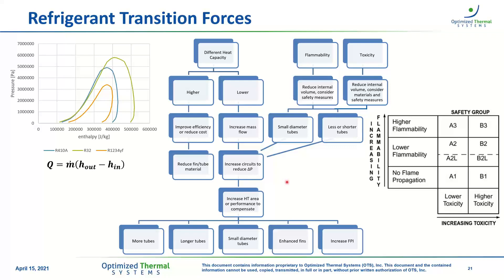The story with flammability and toxicity is similar. When we need to deal with either of these challenges, the solution is usually to try to reduce the amount of refrigerant. Especially for flammability, there are charge limitations in product certifications and building codes we need to consider — we'll often have to minimize the amount of flammable or toxic refrigerant being used. We can do that by putting in smaller tubes, fewer tubes, shortening them — changing the internal volume of the heat exchanger. When we make that change, there will again be a cascade of other changes to both heat exchanger and system-level performance that we need to design around.